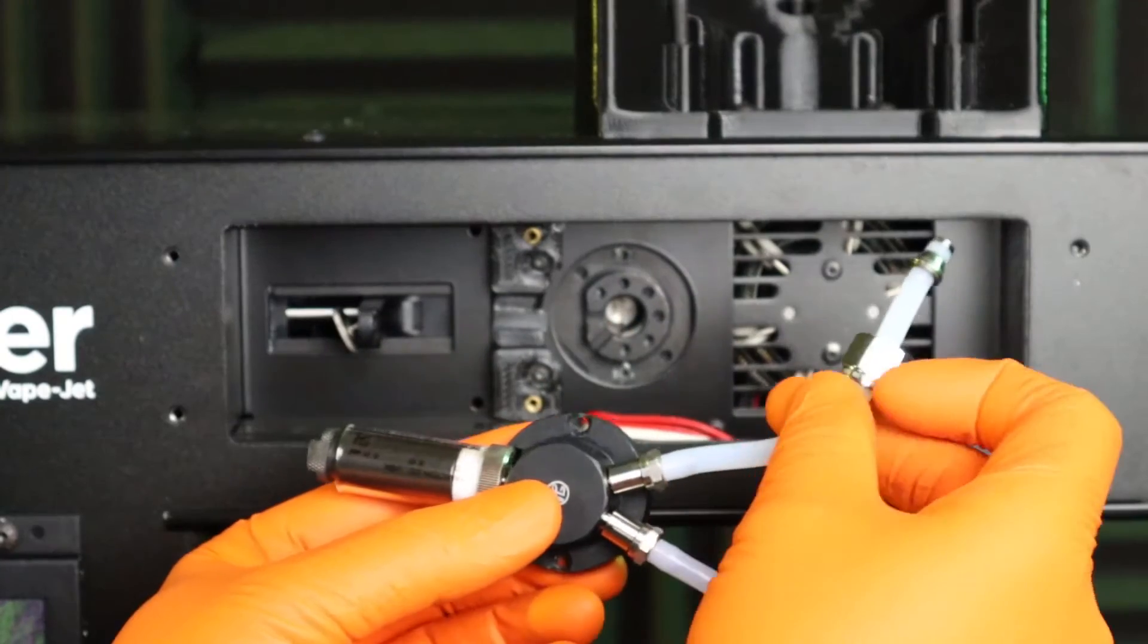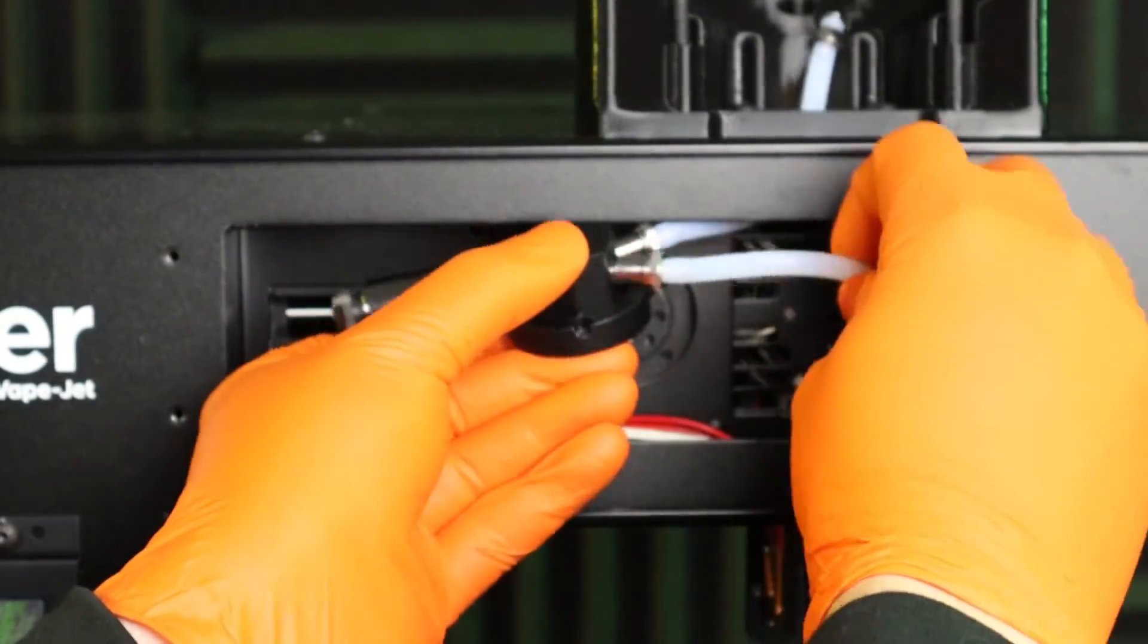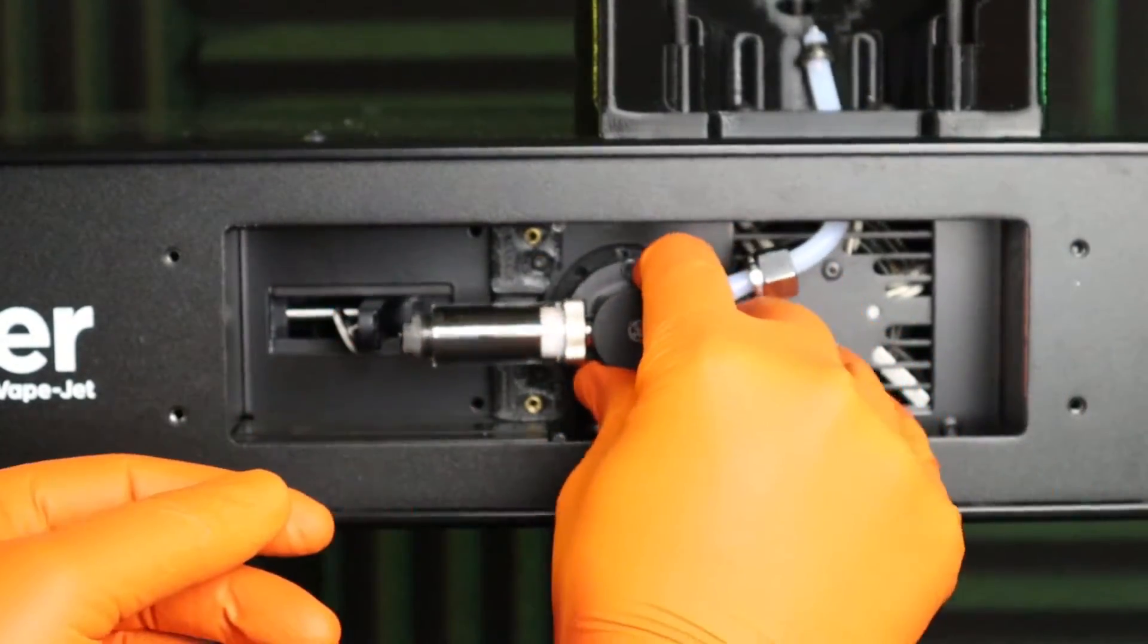If the syringe translation stage is not still at its charged position, go to the advanced screen and click charge under the pump section. Next, push the syringe and valve straight into the mount until fully seated.